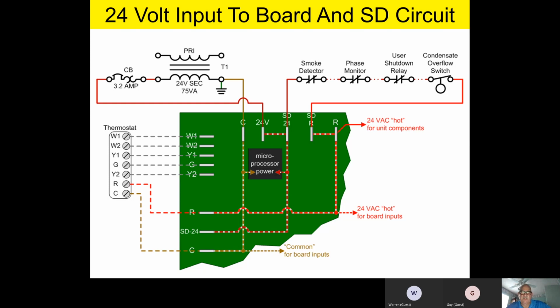So the first thing I always like to talk about is this simplified block diagram of the 24-volt input to the board and the SD circuit. As you take a look at this little block diagram, you'll see there's a transformer, primary and secondary, and that's your 24 volt. It's a 75 VA transformer. It's also protected by a 3.2 amp circuit breaker. And so that voltage at 24 volts goes to 24 V and C.